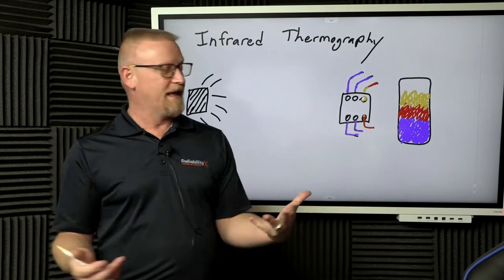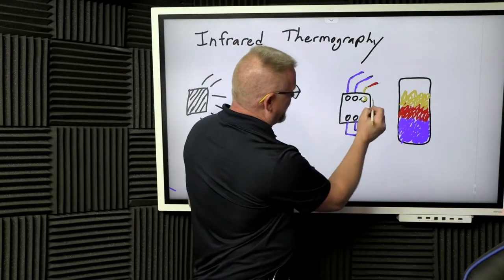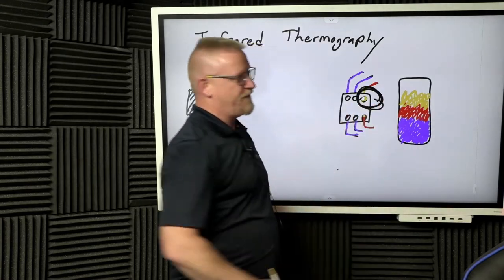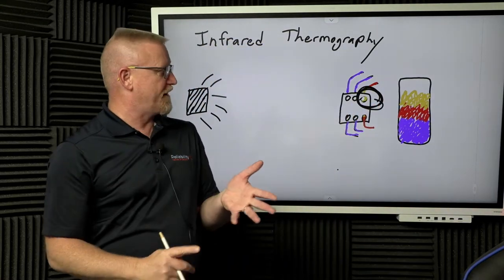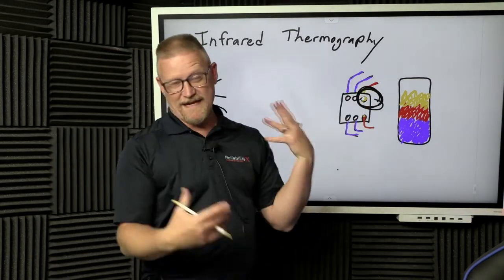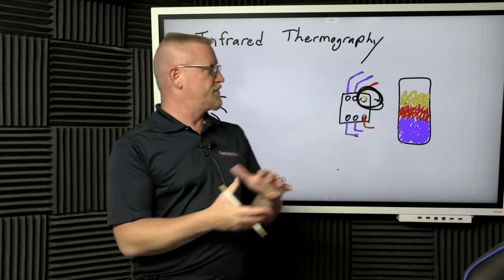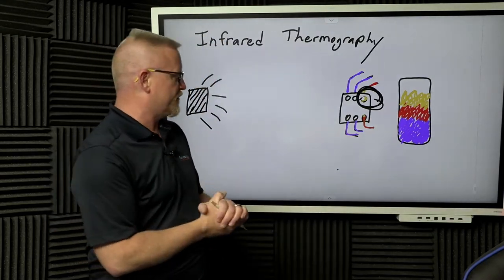When we're looking at things like electrical, we're going to be looking in these areas here and saying, oh my God, I've got some kind of hotspot going on there. Maybe I need to check for load imbalance, maybe a loose connection. But something is definitely hotter in this area than in others, and of course, you should know about what that temperature difference is.